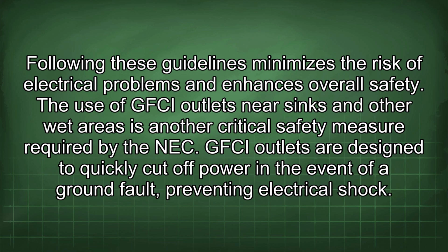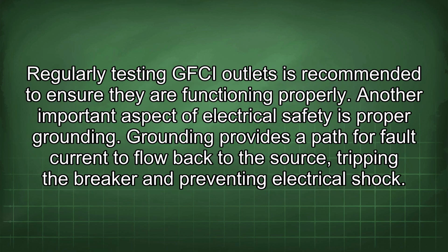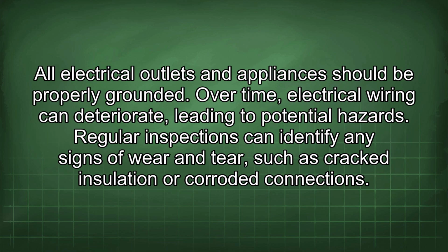The use of GFCI outlets near sinks and other wet areas is another critical safety measure required by the NEC. GFCI outlets are designed to quickly cut off power in the event of a ground fault, preventing electrical shock. Regularly testing GFCI outlets is recommended to ensure they are functioning properly. Another important aspect of electrical safety is proper grounding. Grounding provides a path for fault current to flow back to the source, tripping the breaker and preventing electrical shock. All electrical outlets and appliances should be properly grounded.